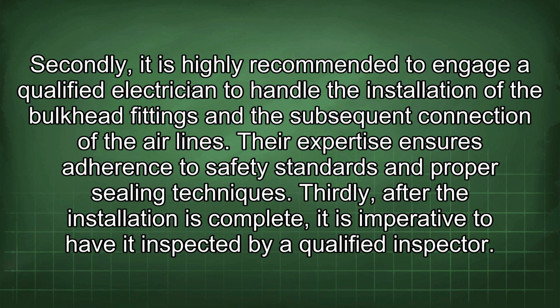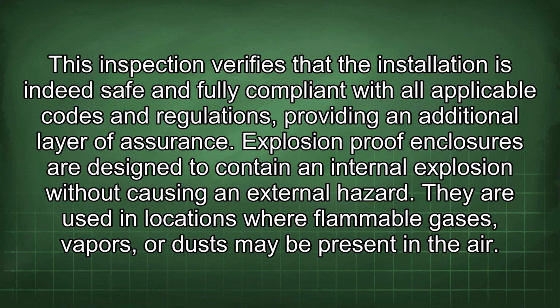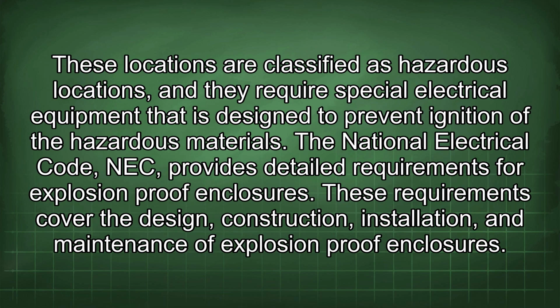Thirdly, after the installation is complete, it is imperative to have it inspected by a qualified inspector. This inspection verifies that the installation is indeed safe and fully compliant with all applicable codes and regulations, providing an additional layer of assurance. Explosion-proof enclosures are designed to contain an internal explosion without causing an external hazard. They are used in locations where flammable gases, vapors, or dust may be present in the air.